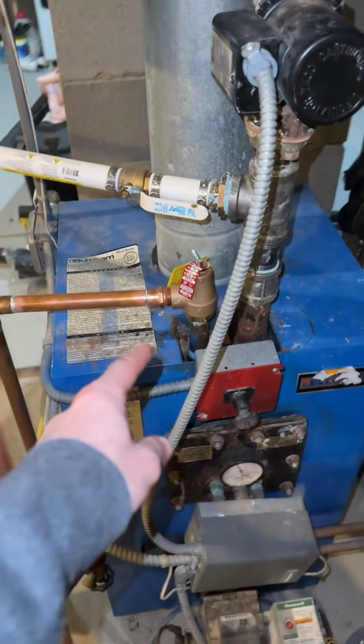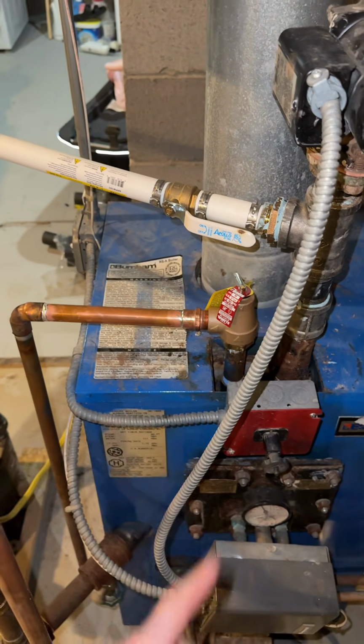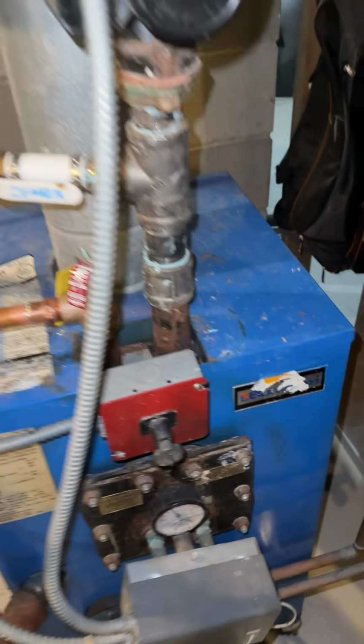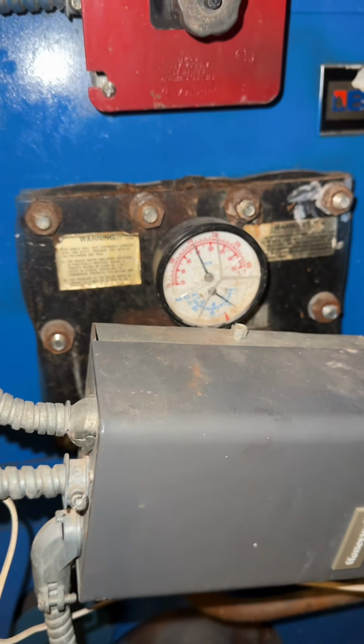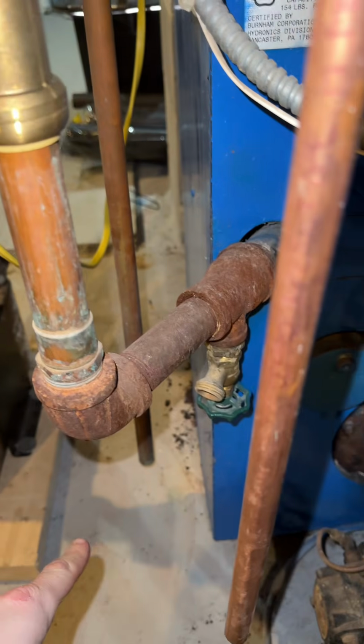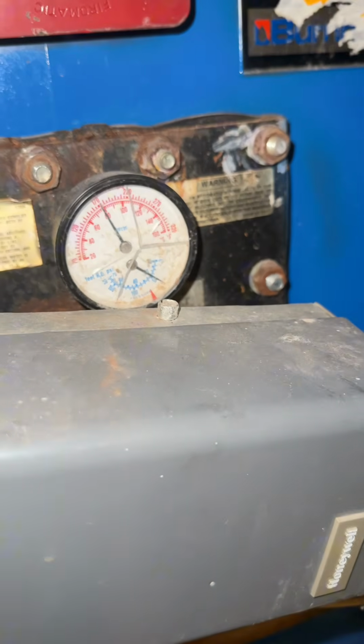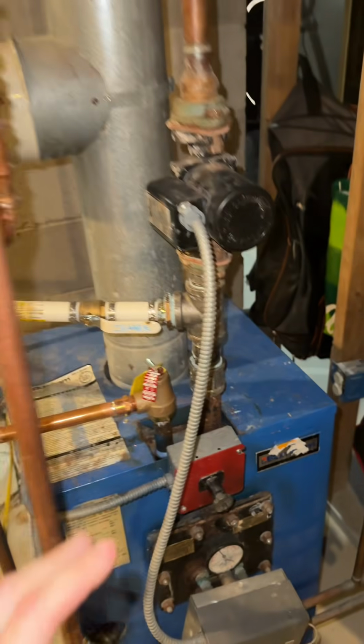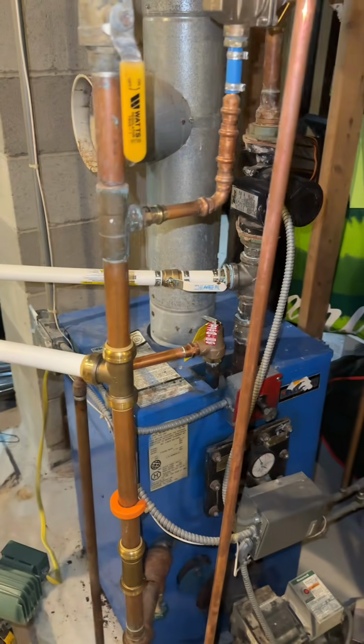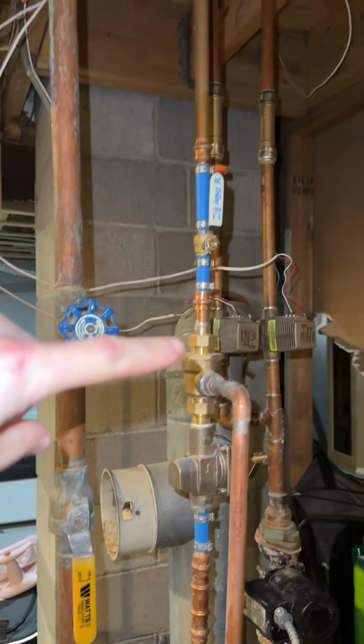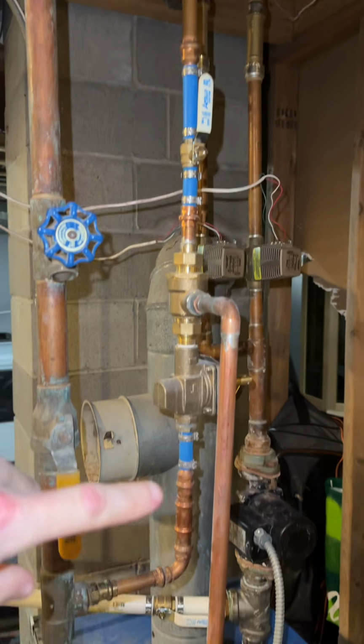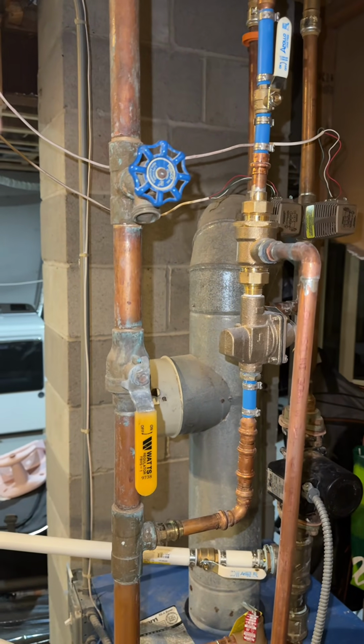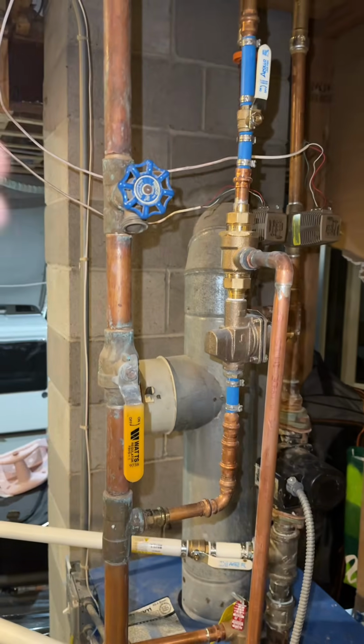One last thing we have is this valve on top. It's a pressure relief valve just in case too much pressure builds up in the system. That will send all the water all over the floor. Awesome. But because this is a pressurized system, it's at like 20 PSI, it's considered a closed loop. You have cold water coming here to this metering valve. So that way there's always pressure in the lines, there's no air, and it's good. It's good to go.